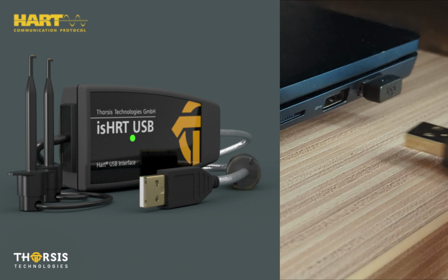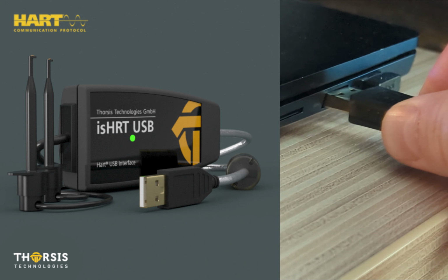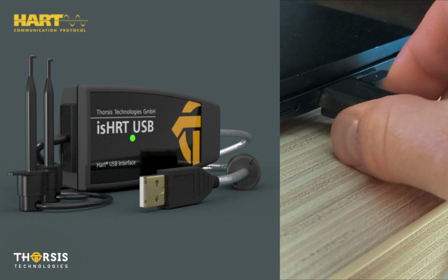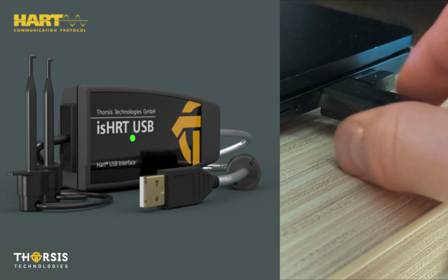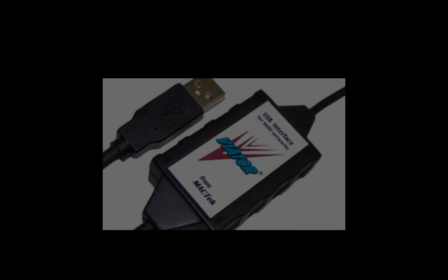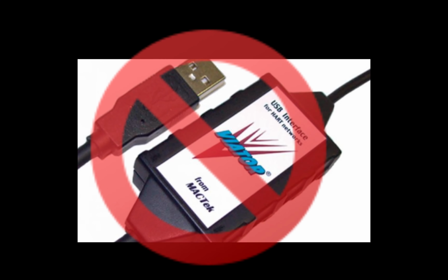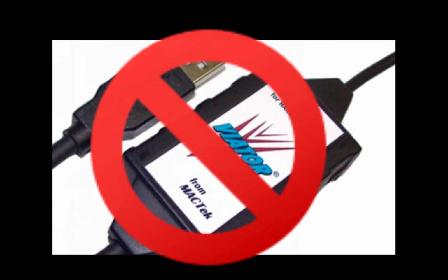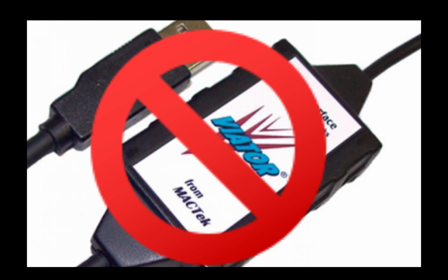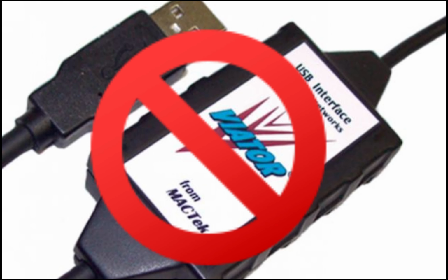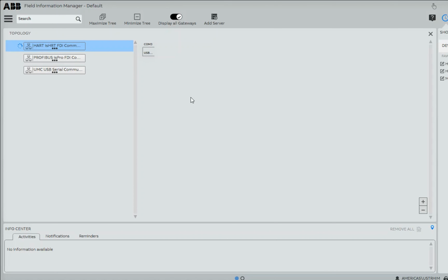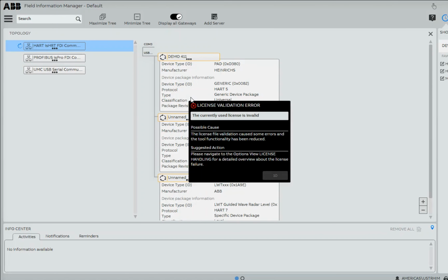If you're using an ABB HART communicator or Thorsis brand, the drivers come pre-installed with FIM. If not, you can now install drivers for your brand of USB HART modems. Note that for legacy Viator brand HART modems, Windows 11 does not support them, so they cannot be used with FIM. Now wire up your devices and plug in the USB.